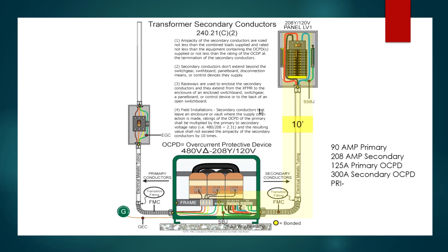For field installations, the secondary conductors that leave the enclosure where the supply connection is made, which is right here, the rating of the overcurrent device of the primary, right here, which was 125 in our case, shall be multiplied by the primary to secondary voltage ratio, which again was 480 divided by 208. Again we rounded it up, 0.5 and higher we round up, so it was 2.307, I believe, so we rounded it up to 2.31. That is our primary to secondary voltage ratio. And that resulting value, in our case, is 125 multiplied by 2.31. So let's do that. 125 times 2.31, and that is 288.75.